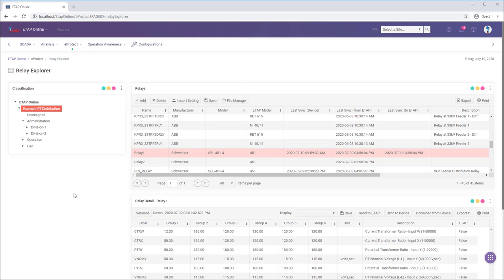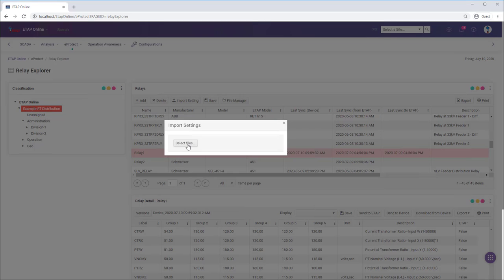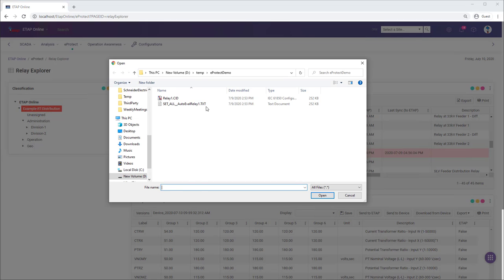eProtect combines a centralized protection asset management system with protection and coordination study results to manage information, optimize settings throughout the lifecycle of the relays and substation assets. We are going to download the settings file, send them to ETAP, and use Star Auto to automatically evaluate the protection settings. First, select which relay we're going to import the settings. These settings come from the actual device through the OEM software or can be configured to come directly from the relay.